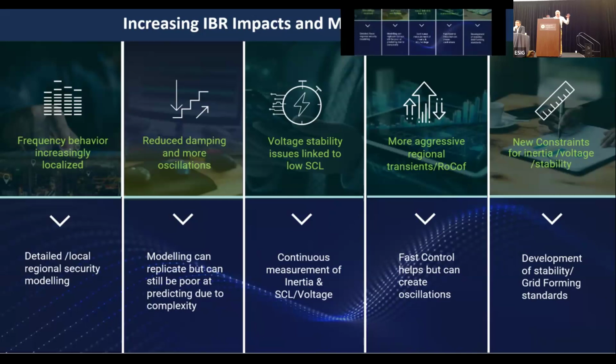So these fast control devices are incredibly important and valuable, and will be the fundamental underpinning of high IBR operation. But you really need to understand how your grid is behaving, understand the natural resonances in it, understand the time constants - and that means, as someone mentioned earlier, hardware in the loop modeling, multiple grid forming controller modeling. All really, really vital. But the frequency is not the same everywhere.